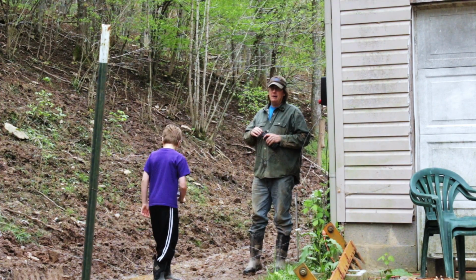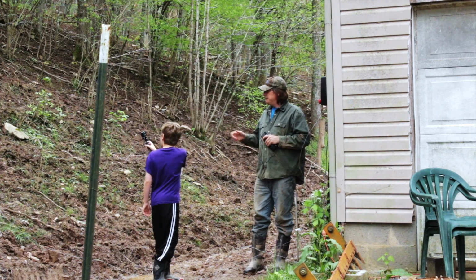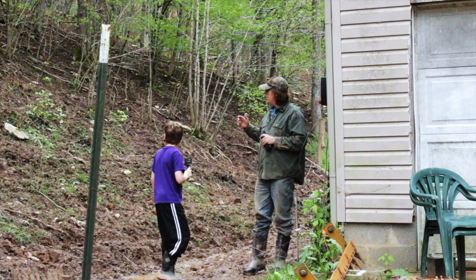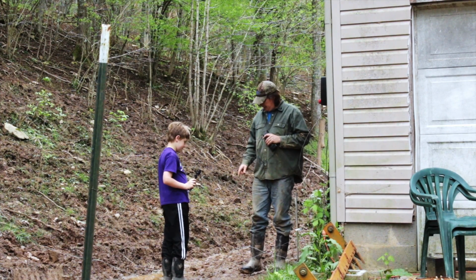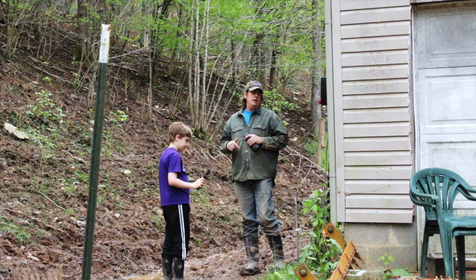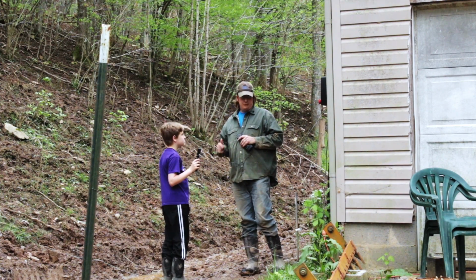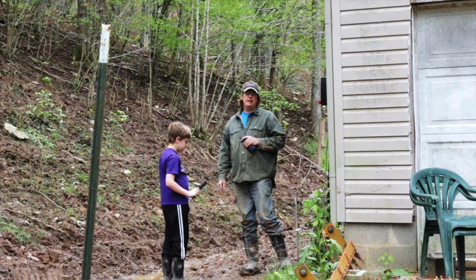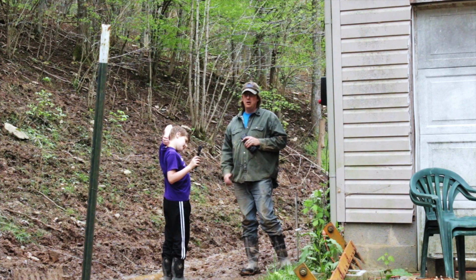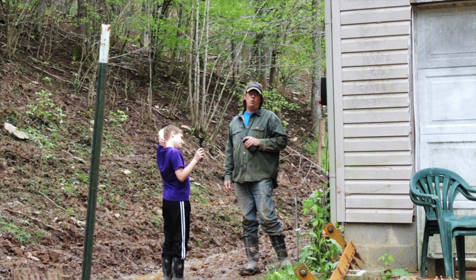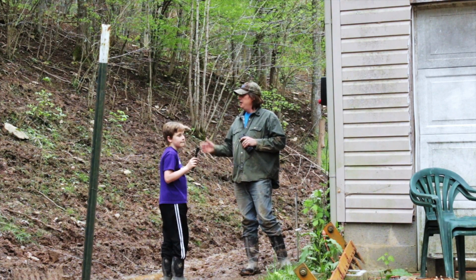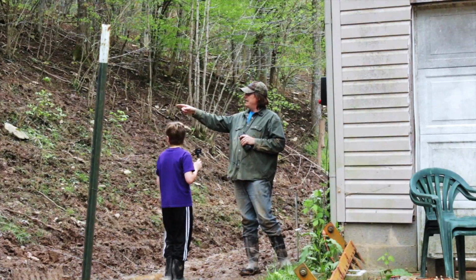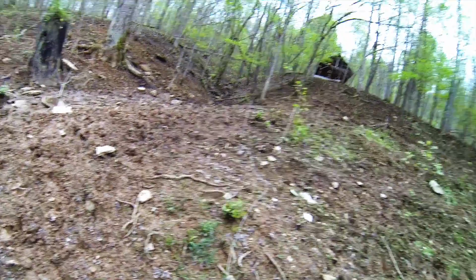Now, in my previous video about the 5 essential things for electric fence hookup, we talked about the difference between an insulated ground wire and a non-insulated one, and I said I've always gone with non-insulated and haven't really seen any issue. Well, this is probably one of those issues. A non-insulated ground is starting to corrode. My connection points with the grounding rods are probably getting a little corroded. There's just not a good contact.